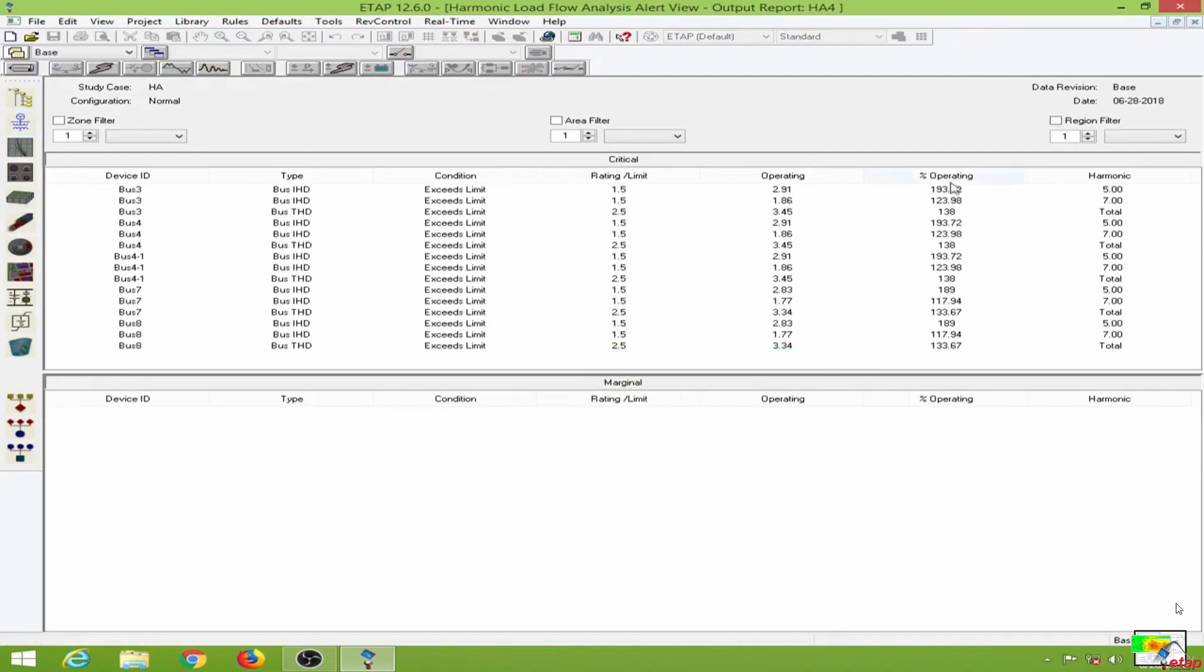This puts me in the critical window. As you can see, all the buses are exceeding the harmonic levels. The rating limits are 1.5, but these are operating at about 2.91.